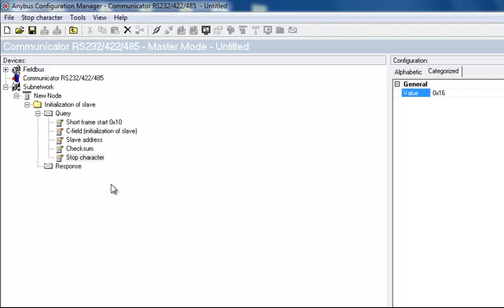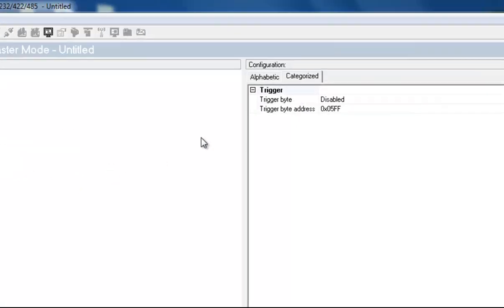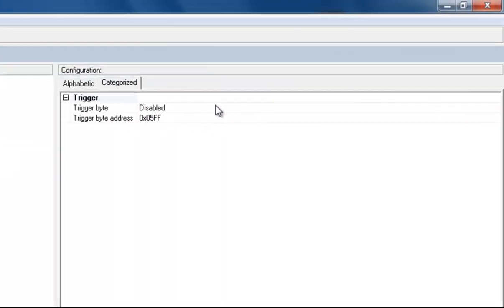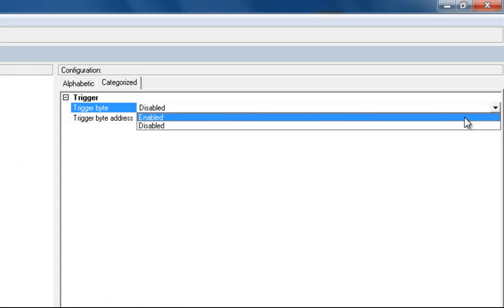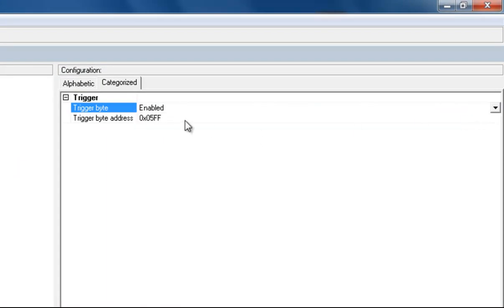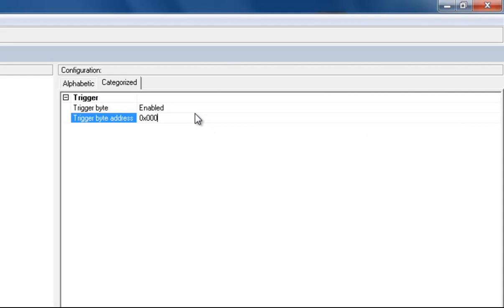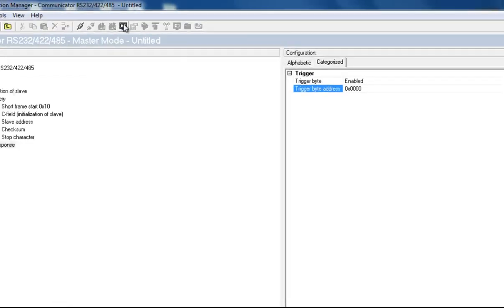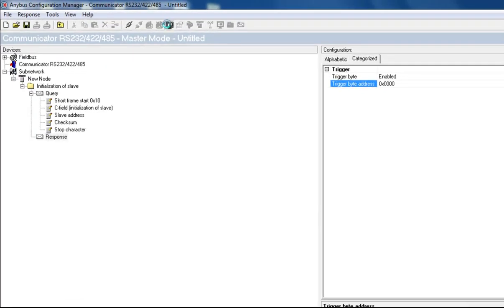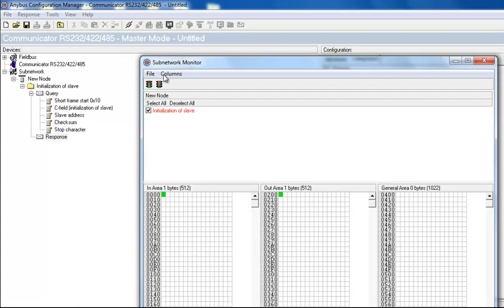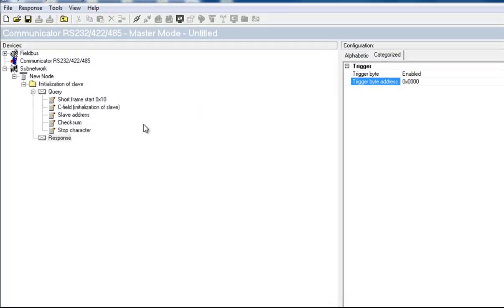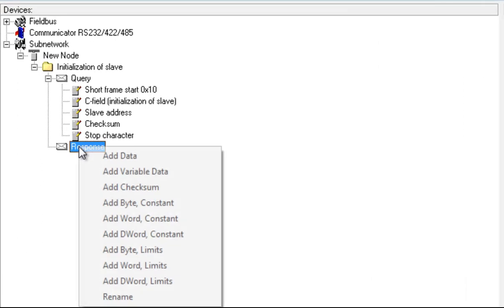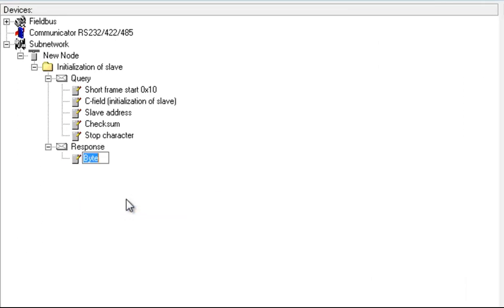I then move on to the response from the energy meter. First, I add a trigger byte, so that we know that we have received an answer. I put this on byte address 0. I open the subnetwork monitor to see that this has been registered in the first byte of our IN area. The response from the energy meter is a byte with the value E5. This means that the slave has been initiated.